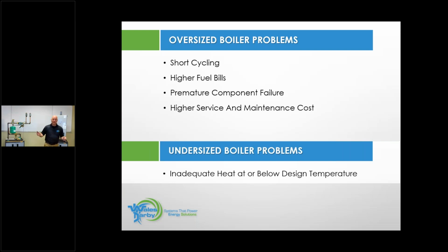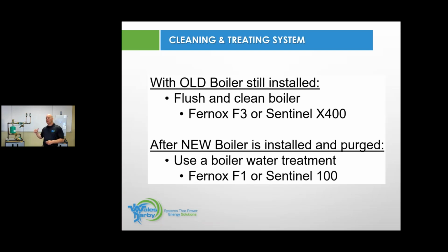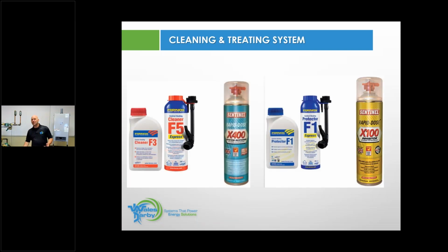Back to that dirty system where we're going to put this, you know, condensing product in. And if you go through and read the manuals, it doesn't matter if it's on a cast iron product or on a condensing product. They're going to tell you to flush the system. Okay, now in the last 10 years or so, we've been introduced to a lot of these different cleaners. They're on the marketplace. We don't rep a cleaning company, so, you know, nothing to do with us here, but there's different brands out there. You look at the manufacturer, the boiler manufacturer's literature, they'll probably recommend 1, 2, or a third brand to put into the system that will clean the system so that that dirt and debris does not make it back into your boiler.